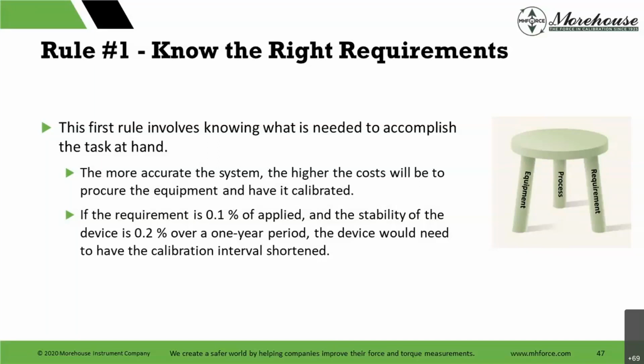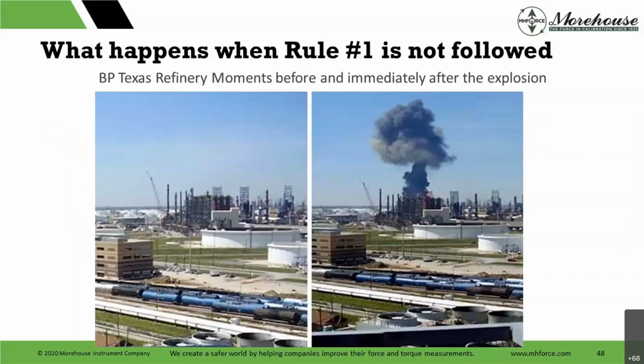If you want to maintain it, every time you send it back to the supplier and they're giving you the fail, not good, right? You can't continue to claim that uncertainty. You can't continue to claim 0.1, because maybe on day one you're actually 0.1% of applied, but at the end of that year, when the calibration provider is doing it again and calling it 0.2, am I really going out at the half year period? Am I going out at three months? Again, about risk. At some point, you're going out and you're passing that risk to the customer.